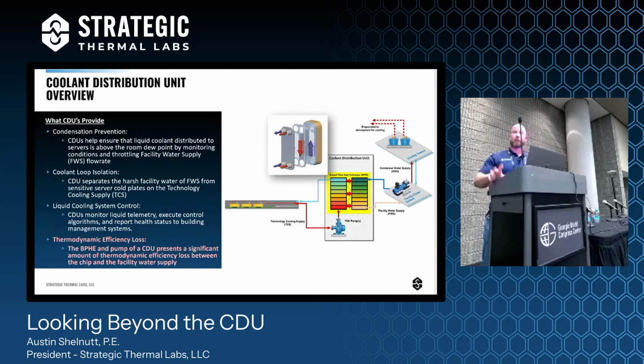CDUs, okay? So cooling distribution units provide a number of wonderful benefits. This is not the anti-CDU campaign. I should have started with this, but at Strategic Thermal Labs, we sell CDUs. So obviously I'm not trying to kill my own market, this just feels like the right thing to do. When we're trying to drop the overall thermal resistance from our processors to the outside air so we can improve energy efficiency across data centers, this is a stone that needs to be kicked over. I believe that as a guy who wants to sell you a CDU. So just putting that out there.